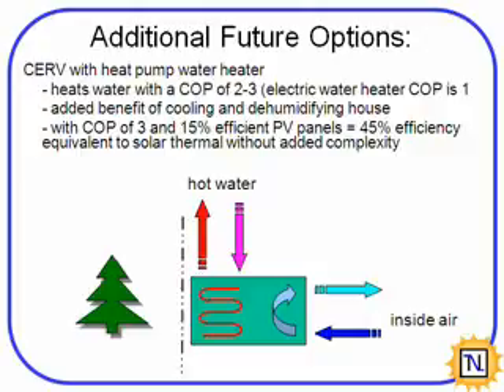Another future option is a heat pump water heater, which you might have heard about, or more talk of them recently. GE announced that within the next few years they'll be releasing a commercial unit for sale. These give a COP of about 2 to 3, where your electric resistance water heater has a COP of just 1, so this is 2 to 3 times better. Using this type of water heater, you also get cooling and dehumidification of your house, which is an added benefit. So the unit would basically be here, circulating your inside air, and then instead of exchanging heat with the outside or the inside, you're putting that into your hot water here.